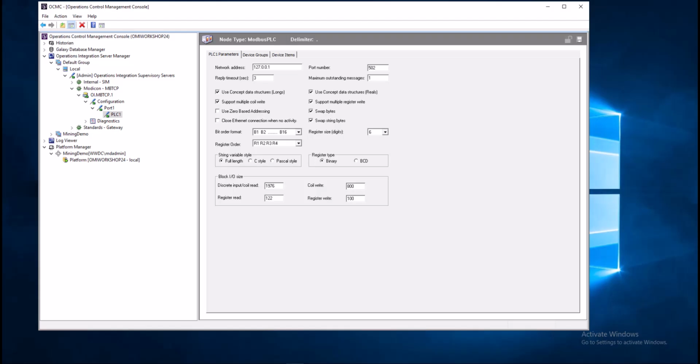We had a customer who wanted to expose data directly from an AVEVA OI server to OPC-UA. At the current moment, the AVEVA OI drivers, like the OI MBTCP or the Rockwell ABCIP driver, are OPC-DA compliant, but not OPC-UA compliant. So they couldn't act as an OPC-UA server and read the information directly. So we're going to talk about a method where we can extract the information.